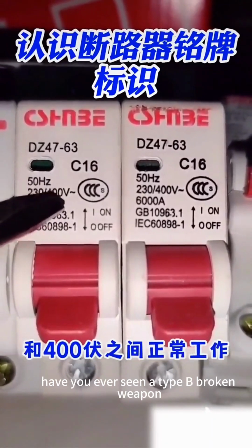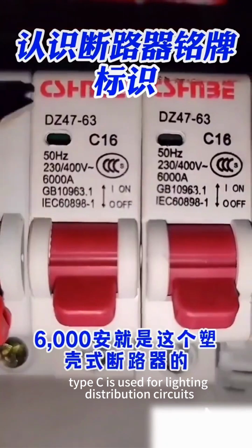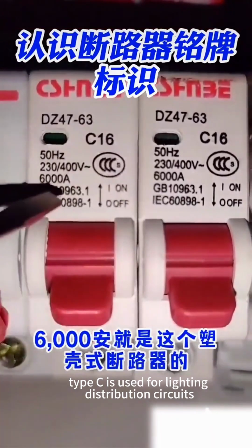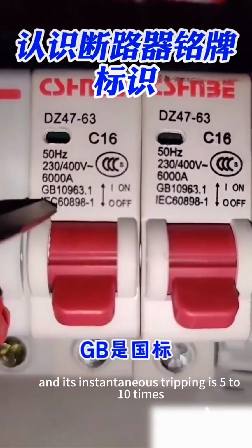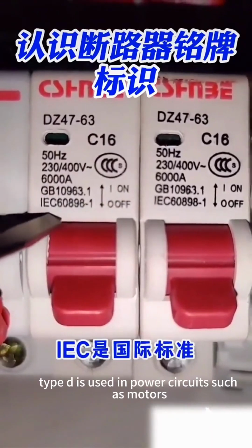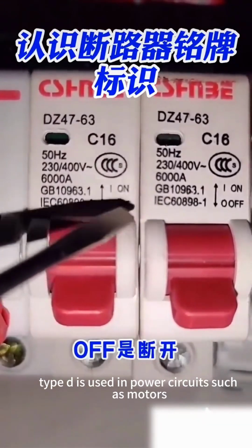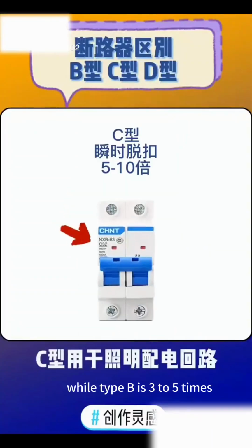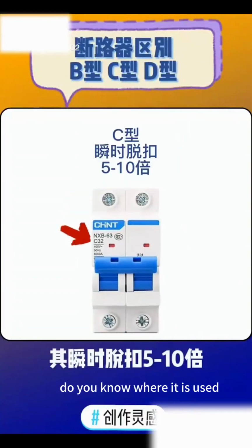Have you ever seen a Type B circuit breaker? Type C is used for lighting distribution circuits, and its instantaneous tripping is 5 to 10 times the rated current. Type D is used in power circuits such as motors. Its instantaneous tripping is 10 to 14 times, while Type B is 3 to 5 times. Do you know where it is used?